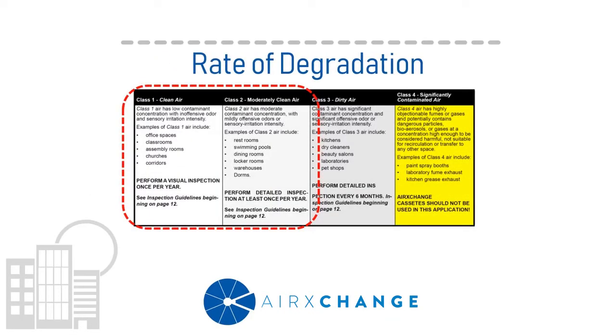So to assist folks and give them a relative idea of what the potential rate of degradation will be, we have developed this chart, which is included in our operations and maintenance manual. It's based primarily on the ASHRAE classifications of air. The majority of building spaces are going to be subject to class 1 and 2 air. This would equate to a low to moderate rate of degradation. And as you move over to a class 3, the rate of degradation is going to increase. And for class 4 air, where wheels aren't typically employed, you shouldn't have to be concerned with that particular class.